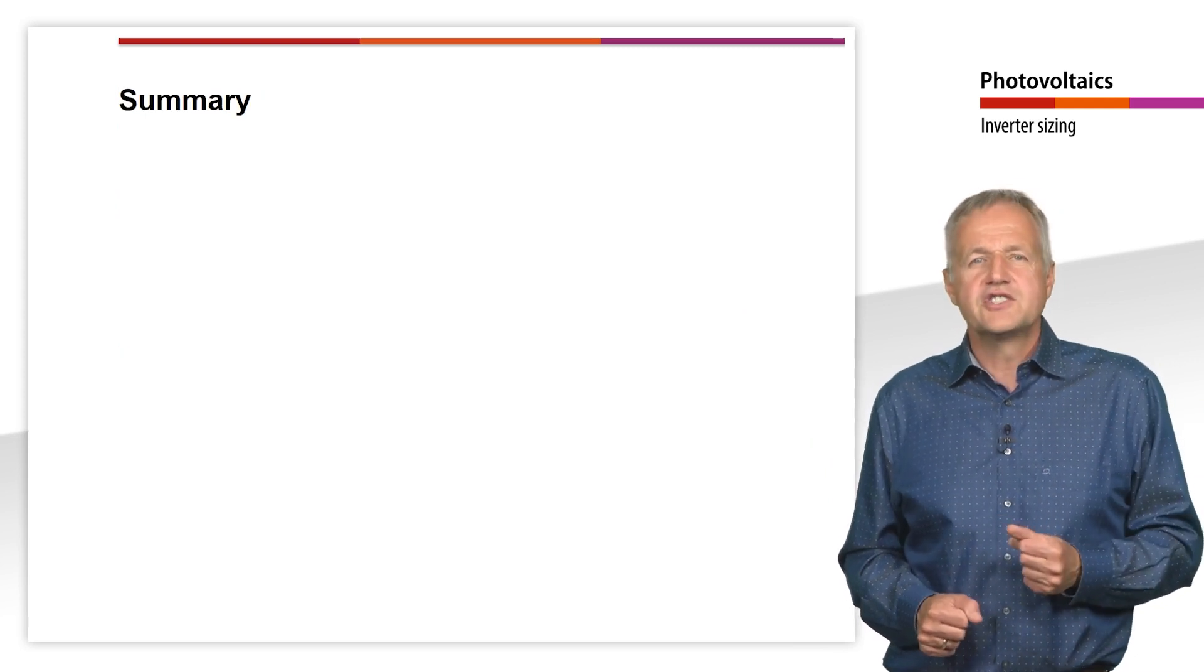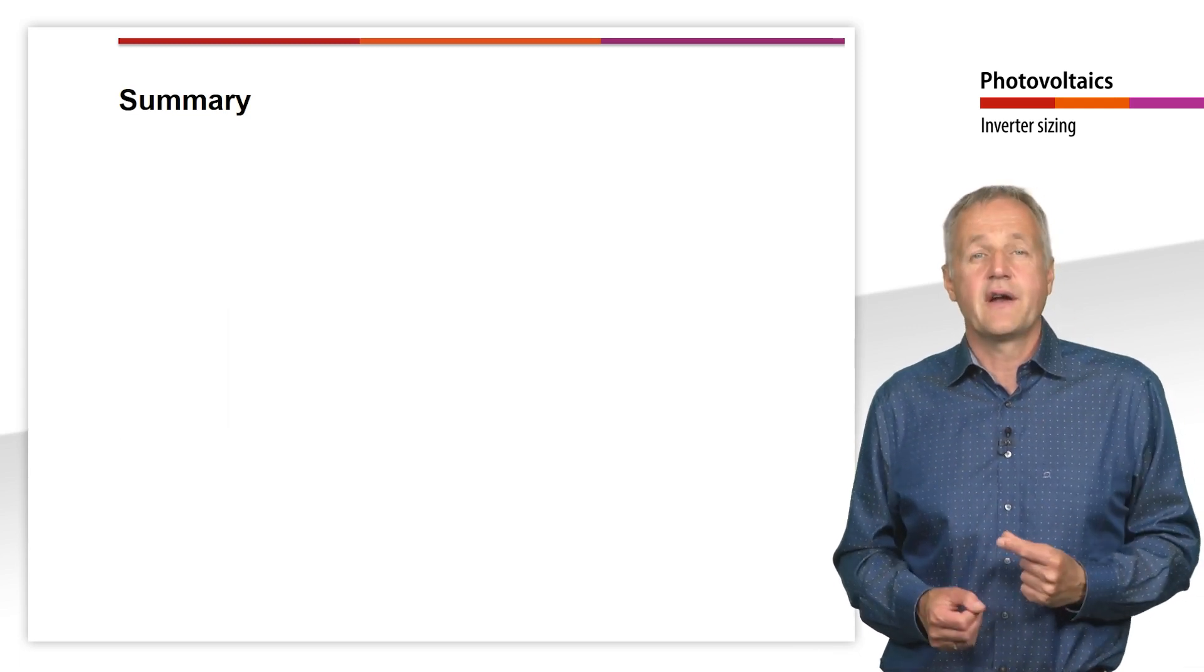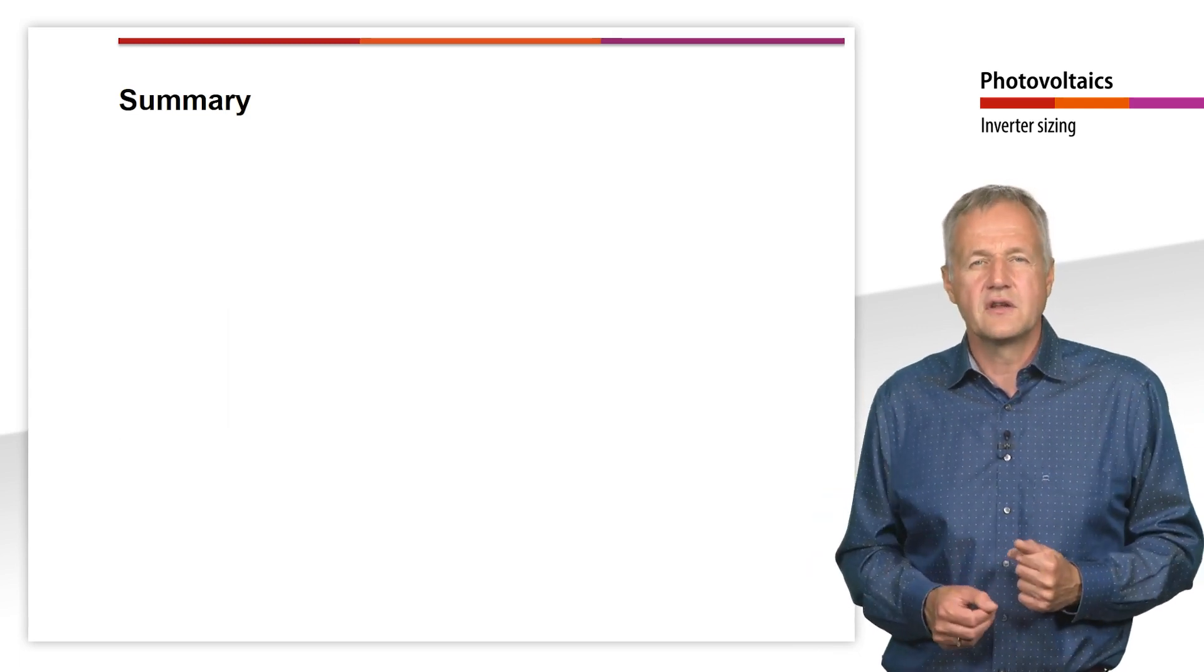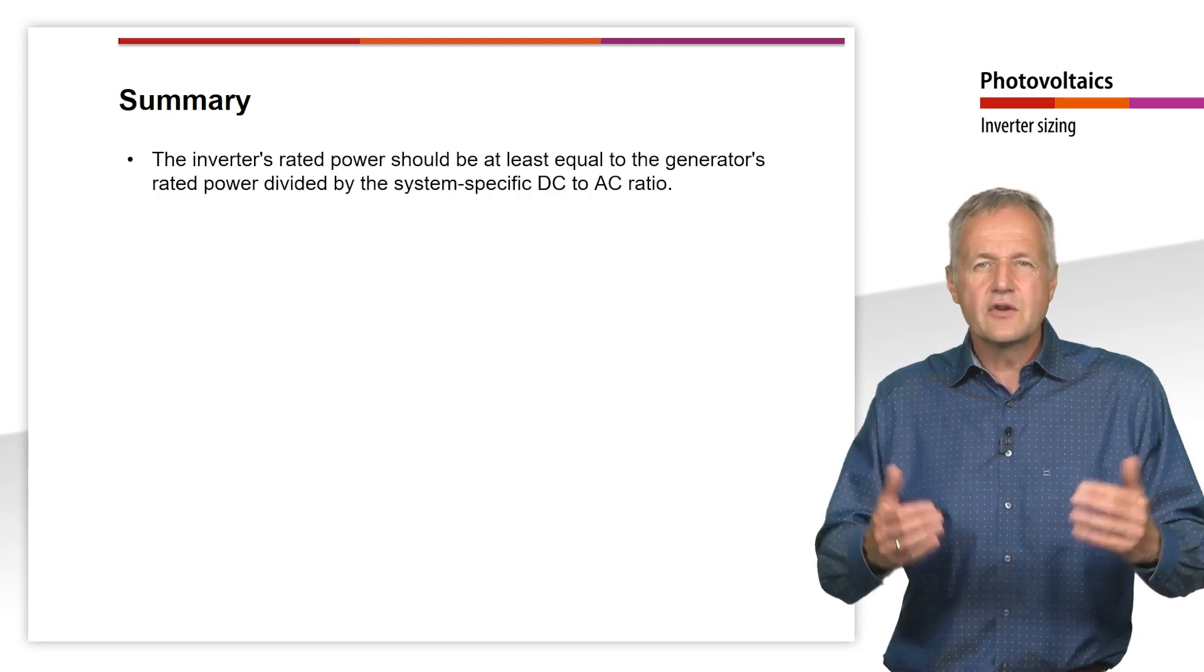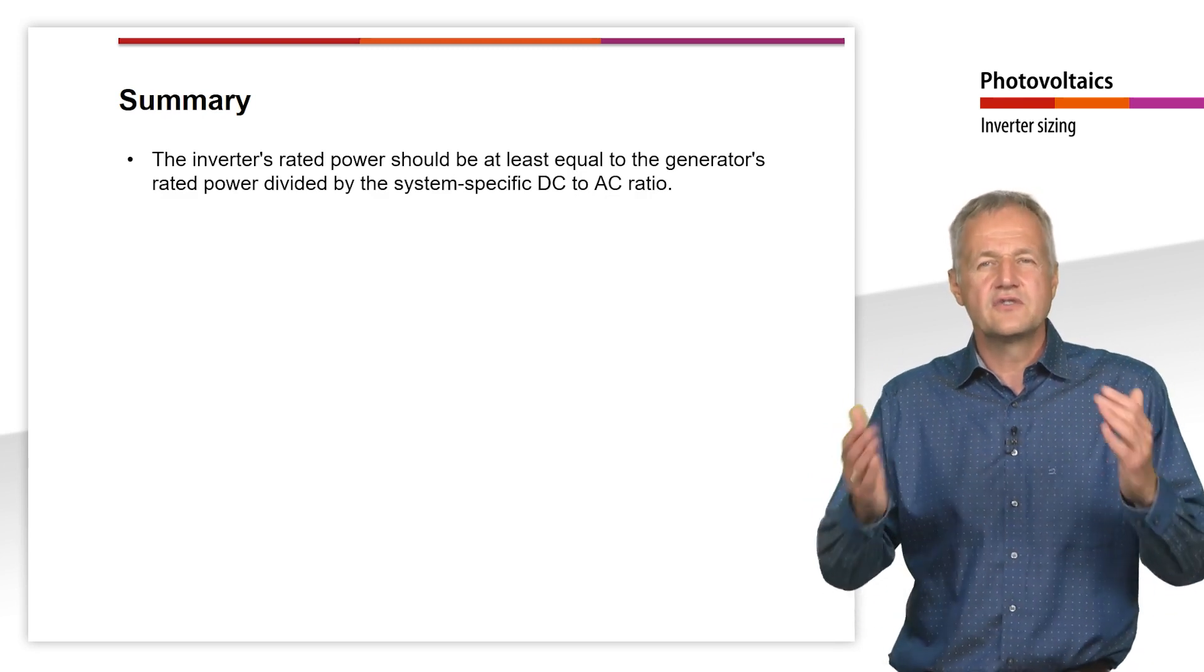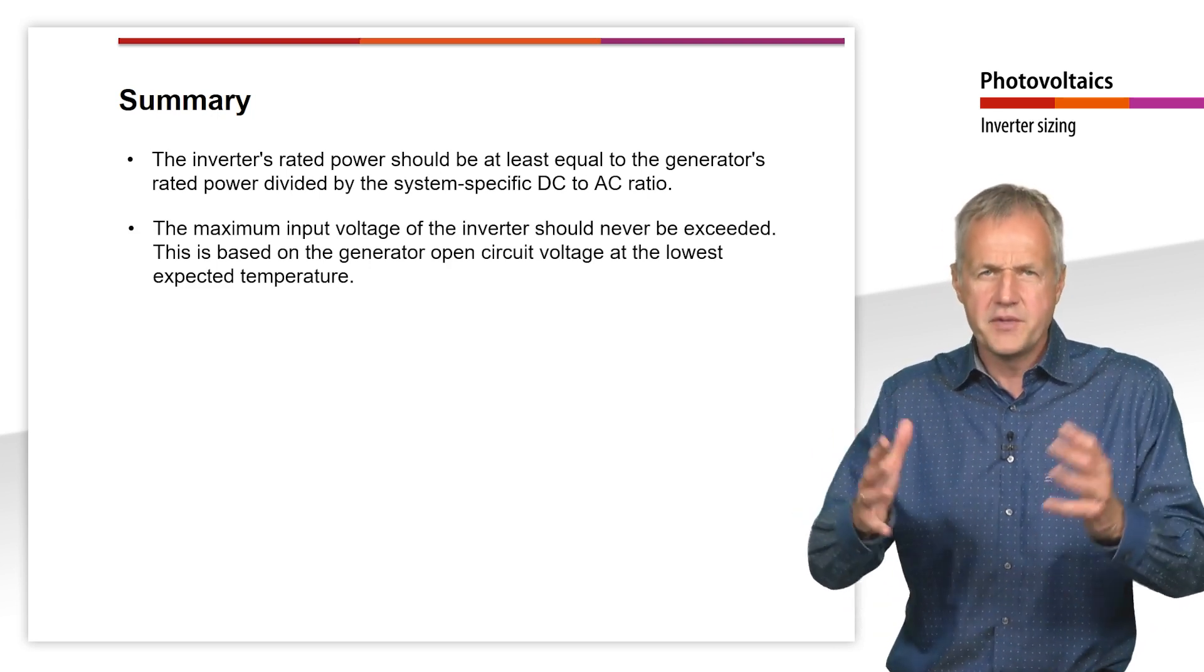Let's summarize this teaching unit. We have learned about three essential criteria for sizing the inverter. The inverter's rated power should be at least equal to the generator's rated power divided by the system-specific DC to AC ratio. The maximum input voltage of the inverter should never be exceeded.